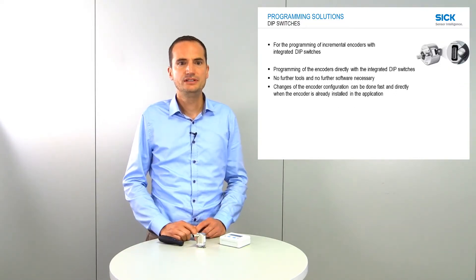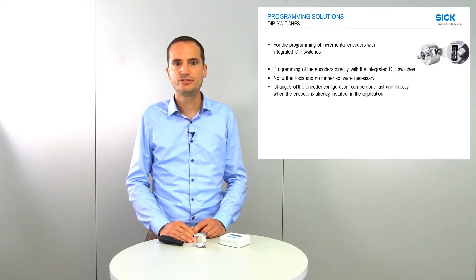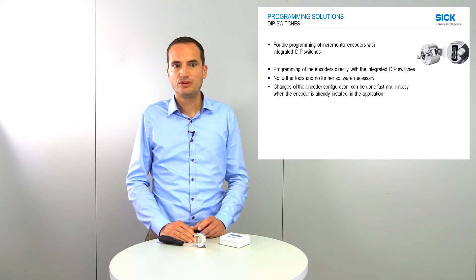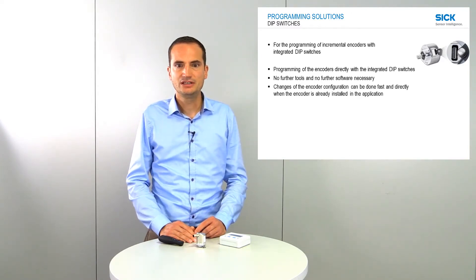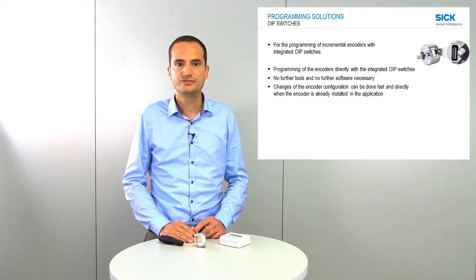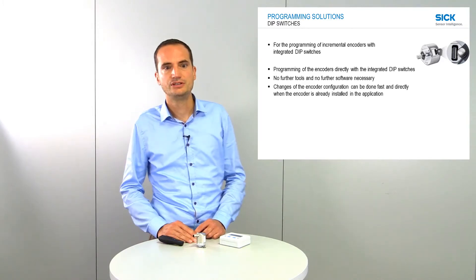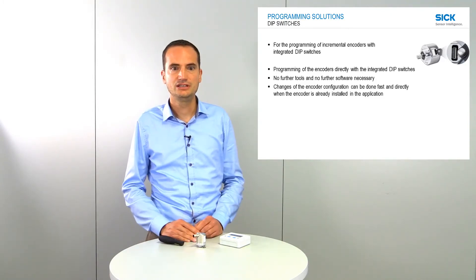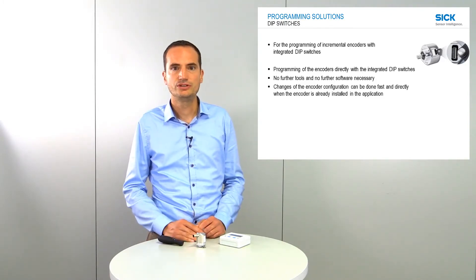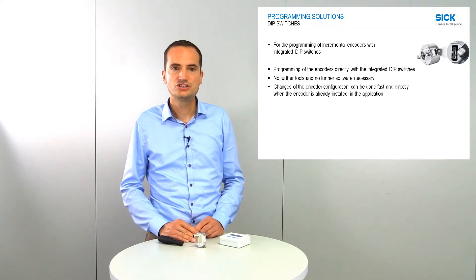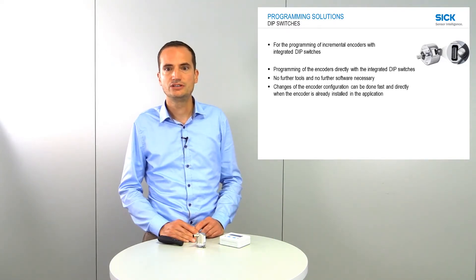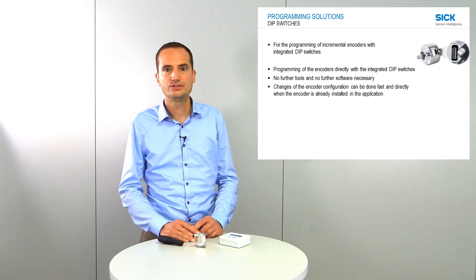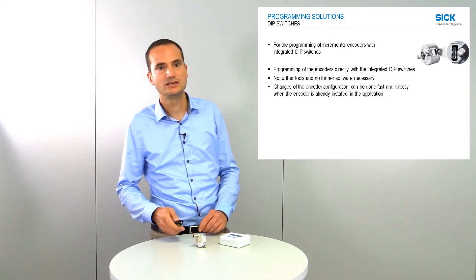Another programming possibility is the so-called DIP switches. This is for the programming of incremental encoders with integrated DIP switches. Programming is done directly by setting different combinations of DIP switches, and you do not need any further tools or software. Changes to the encoder configuration are done directly in the application. You can change, for example, the resolution, the electrical interface (TTL or HTL), and also the counting direction of the incremental encoder.